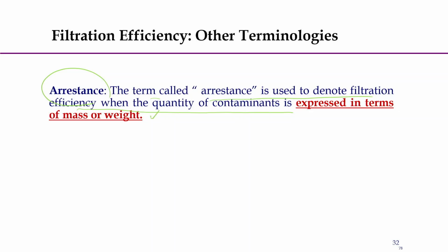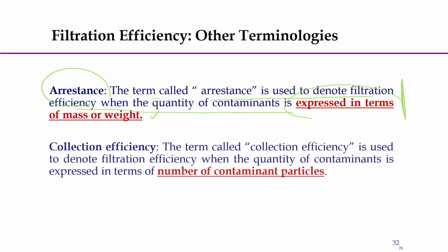It is also filtration efficiency, but if we say arrestance percent, we intend to say that the filtration efficiency is measured based on mass.